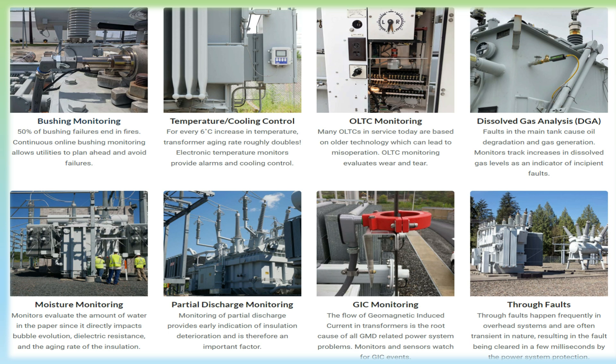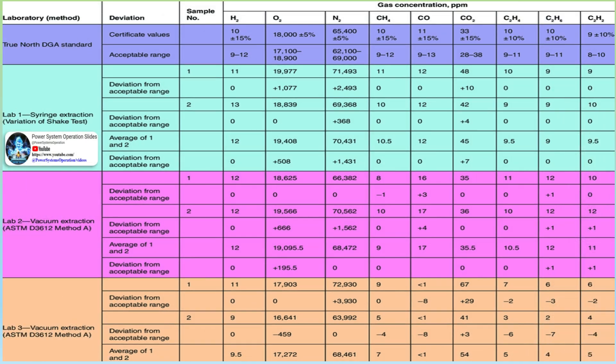Regarding the advantages and disadvantages of key gas monitoring: hydrogen gas alone doesn't provide enough data to perform a diagnosis as to the type of fault occurring. But it is effective at providing an early indication of incipient faults, thereby reducing the chances of a transformer failing without some advance warning, allowing for better management of assets. Key gas monitoring, when used in conjunction with a good maintenance program consisting of routine DGA sampling and electrical testing, offers a dependable, cost-effective alternative to multi-gas monitoring.